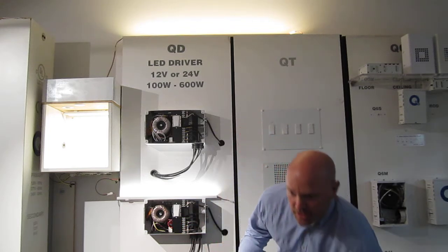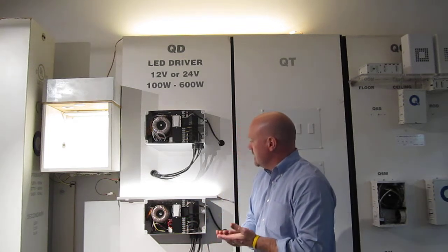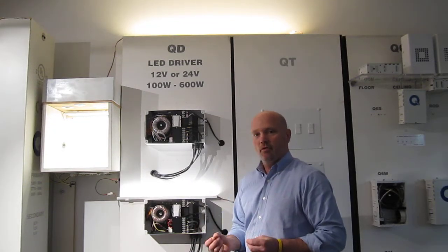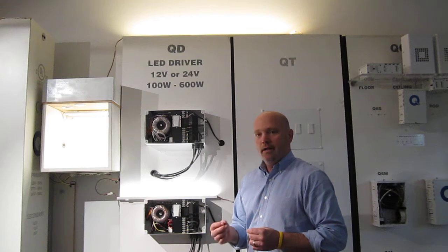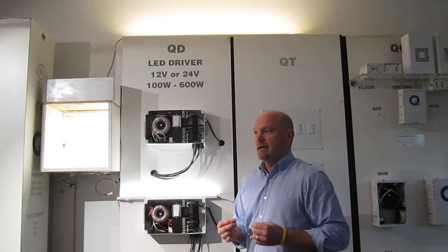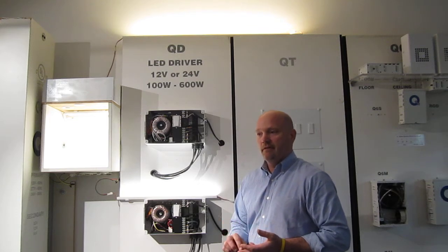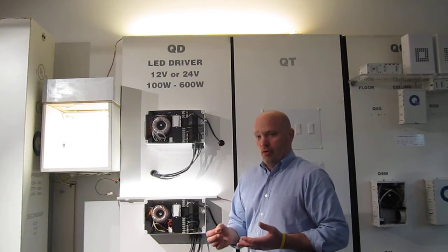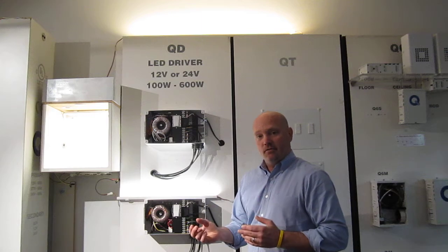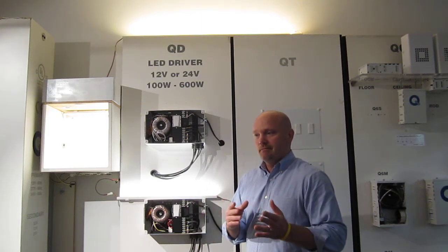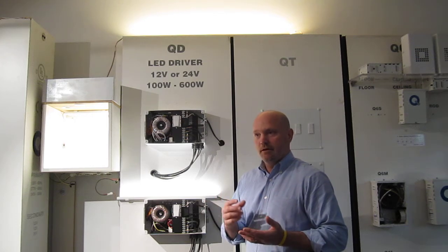Now the next challenge in LEDs is controlling them. With a typical LED driver, you need to use what's called 0 to 10 volt dimming, which is an antiquated dimming system. It's an analog system, not very reliable. Typically you get very little control for the first volt and a half and the last volt and a half on that 10 volt range. And what that causes is you get some inconsistencies in the dimming itself.